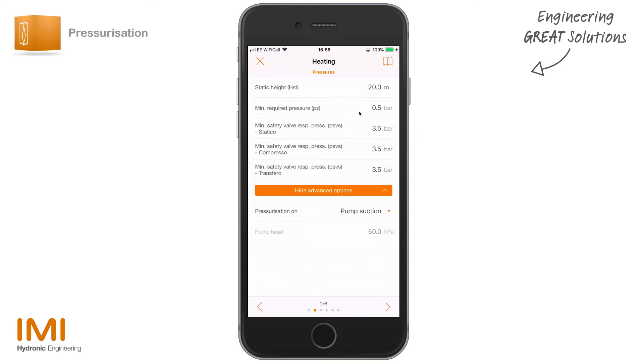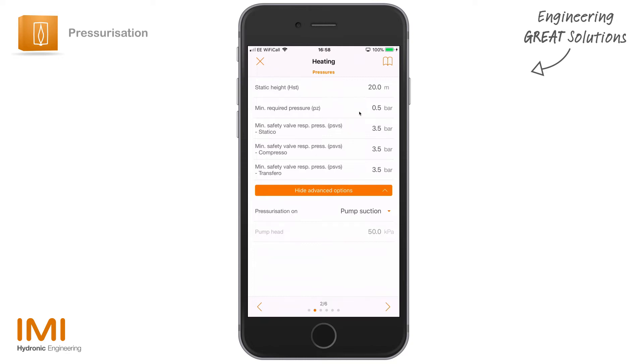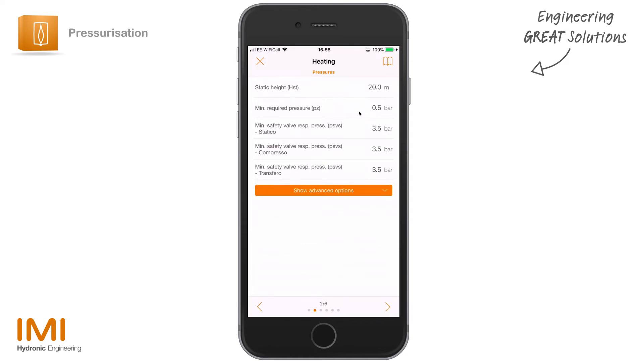If we click on the advanced options here, it gives us the option to place the pressurization in a different location. Typically, pressurization should be at the neutral point — the point of connection should be on the outlet of the pump, not on the suction side. If you choose to put it on the suction side of the pump, it is physically and technically possible, but in that instance you need to add the total amount of pump head being generated in order to stabilize your neutral point pressure adequately. We'll leave this more traditional and keep the pressurization connected on the outlet of the pump, and hide those advanced options.